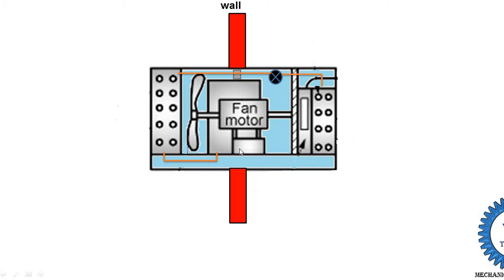The unit is divided into two parts by the wall where it is installed. One is the indoor part and the other is the outdoor part. In the indoor part there is the evaporator, evaporator blower, and expansion device. Outside the wall is the condenser, because the condenser rejects heat to the atmosphere, while the evaporator absorbs heat from the room space.